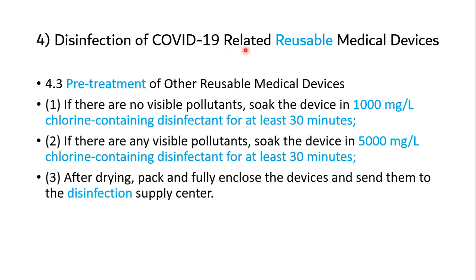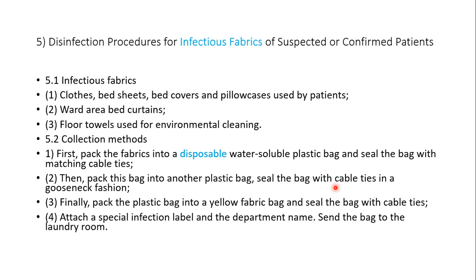Disinfection of COVID-related reusable medical devices. Pre-treatment of the other reusable medical devices: if there are no visible pollutants, soak the device in 1000 milligrams per liter chlorine-containing disinfectant for at least 30 minutes. If there are any visible pollutants, soak the device in 5000 milligrams per liter chlorine-containing disinfectant for at least 30 minutes. After drying, bag and fully enclose the devices and send them to the disinfection supply center.